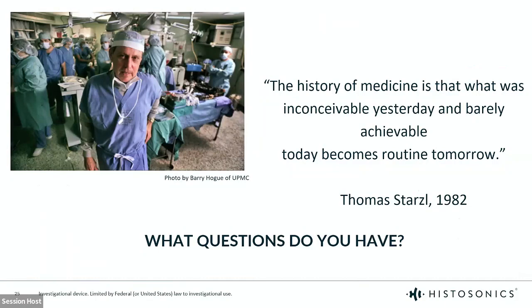We have done a lot of research in animals to ensure that when you're treating through the rib, you're not delivering so much energy that you would heat the bone. There will be some absorption of the energy. When you're doing your treatment, you are actually dosing on those spots based on that. So the real challenge has been, for the most part, not the bone blockage per se in the energy delivery, but the bone blockage in terms of seeing. And we believe, at least initially, the first step towards that is the image fusion. Having said that, if you're all covered by bone, we might have some issue.